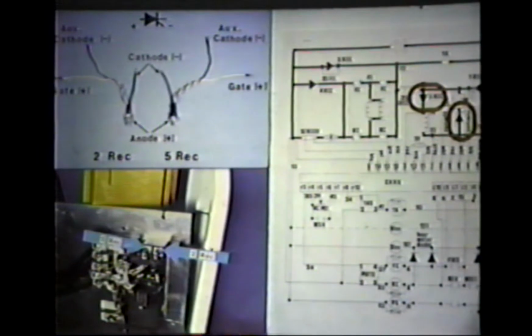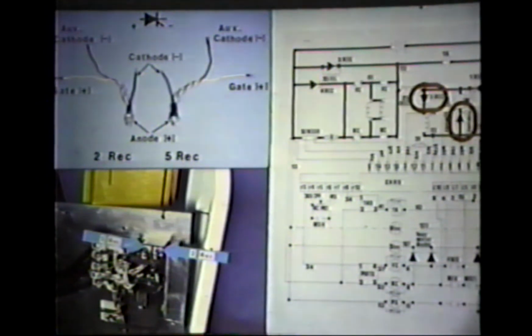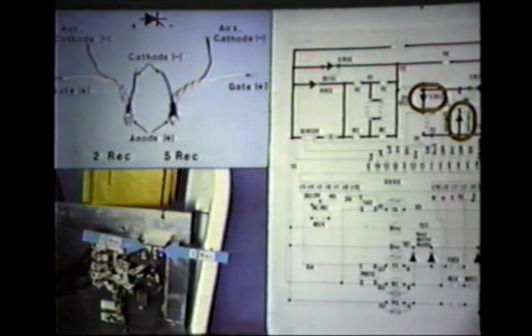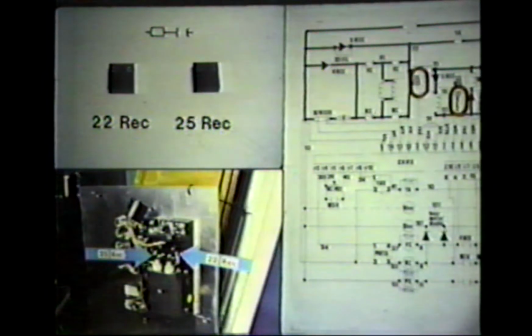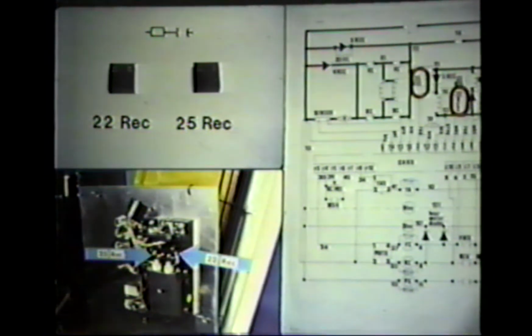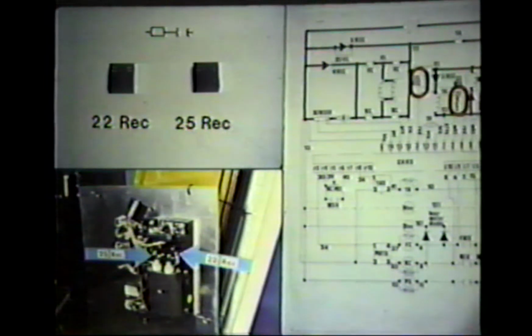Both 2 and 5 recs have a stud or anode terminal, a white gate lead, a black cathode, and a red auxiliary lead. These SCRs are mounted on the end of the panel, with the 2-rec being slightly larger than the 5-rec. Two snubbers, labeled 22 and 25 recs, are connected in parallel to 2 and 5 recs. Inside the blocks are resistors and capacitors used to suppress voltage spikes that may occur during circuit operation. Both snubbers are identical and interchangeable.